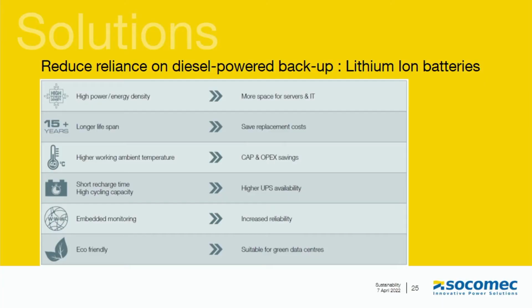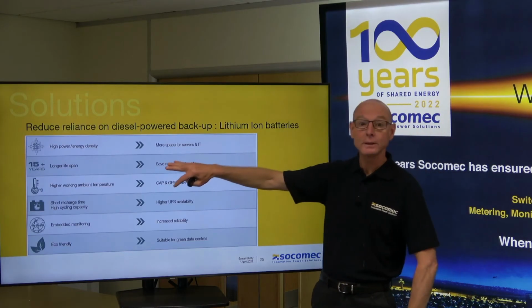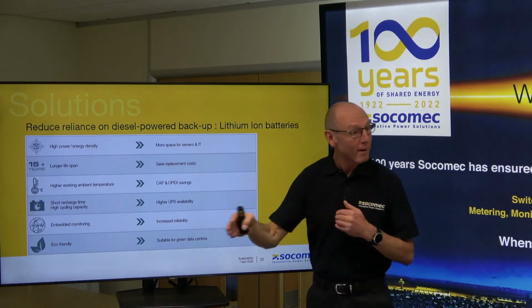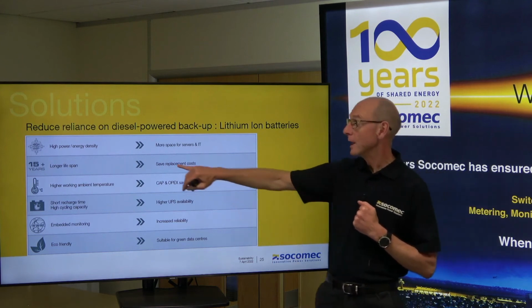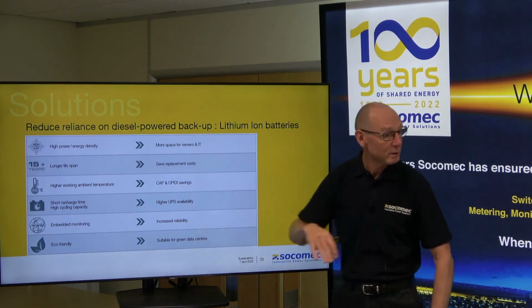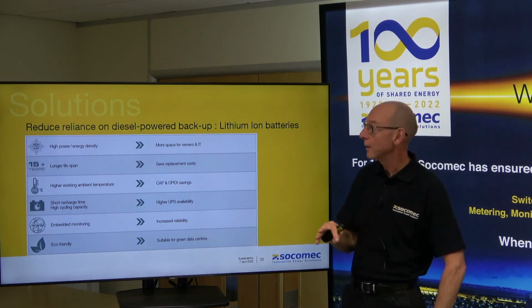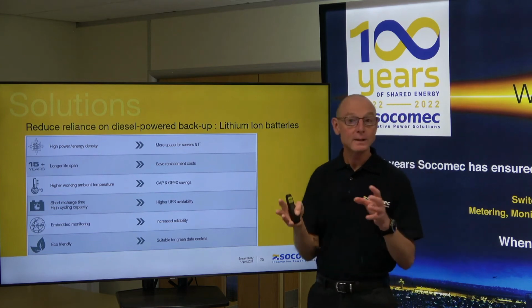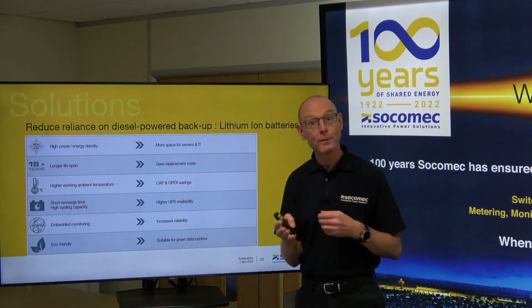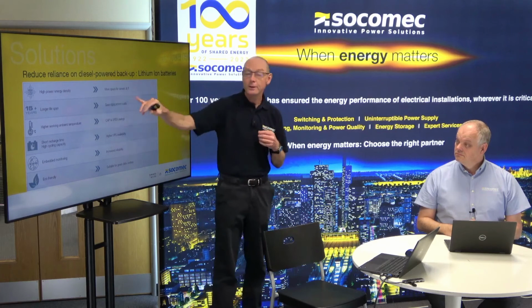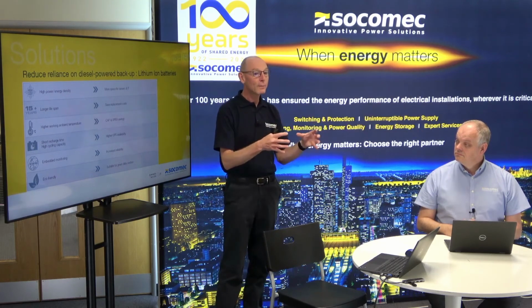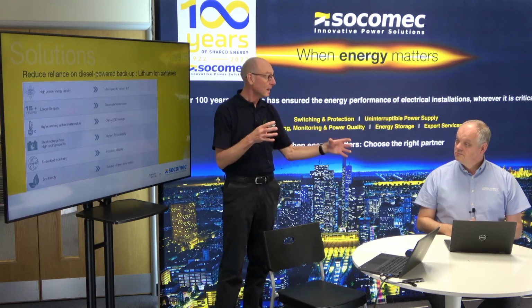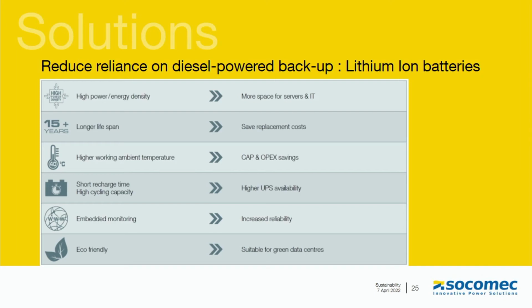Such that you can increase the runtime of the UPS and reduce the requirements and demand on the diesel generators. Lithium-ion technology has increased and is moving at a very, very rapid rate. We're now looking at 15 years plus, 20 years plus life expectancy on lithium-ion batteries. The energy density is much higher than the typical VRLA batteries, meaning you can get more runtime available in the same space, again reducing the requirements on diesel generators.